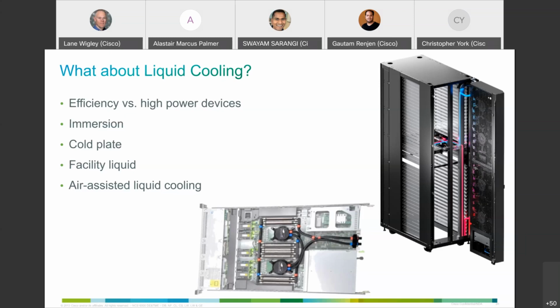The other approach is a rear door heat exchanger, or a heat exchanger in a rack next to it, which is sort of what we're seeing here. The idea is you're using the liquid inside the rack, going into the servers or the router, but you're still turning that back into hot air at or near the rack. So it doesn't give you as much efficiency as chilled facility water, but it does give you the benefit of handling hotter chips.